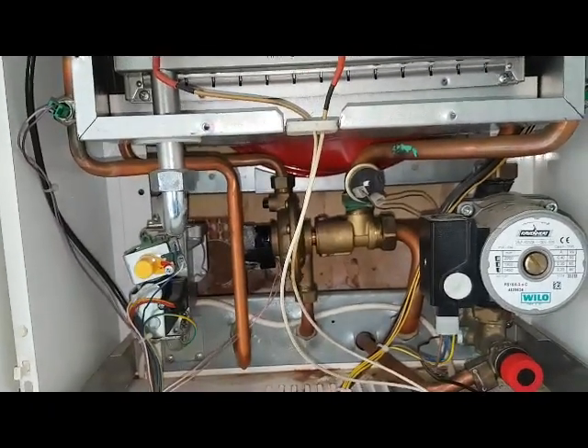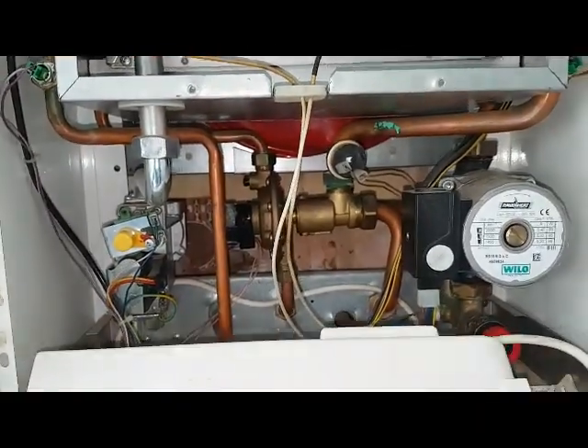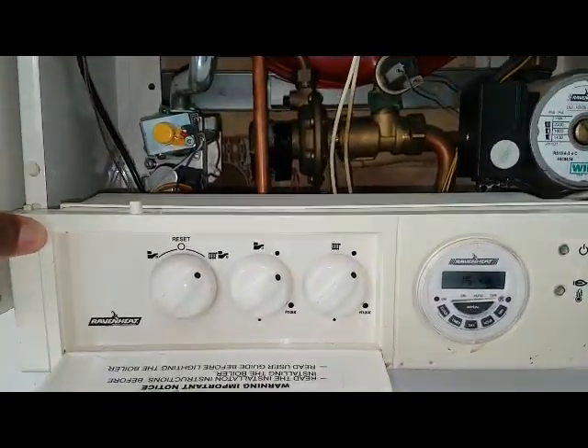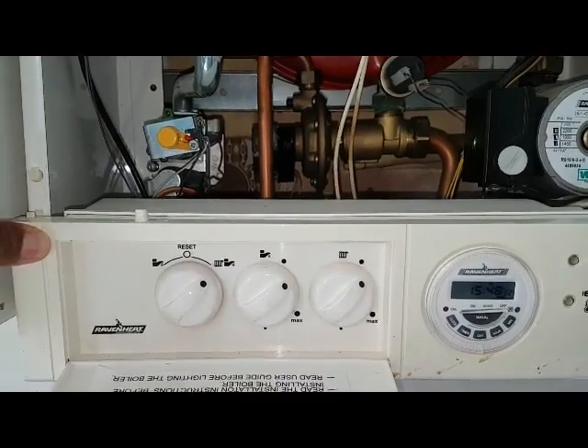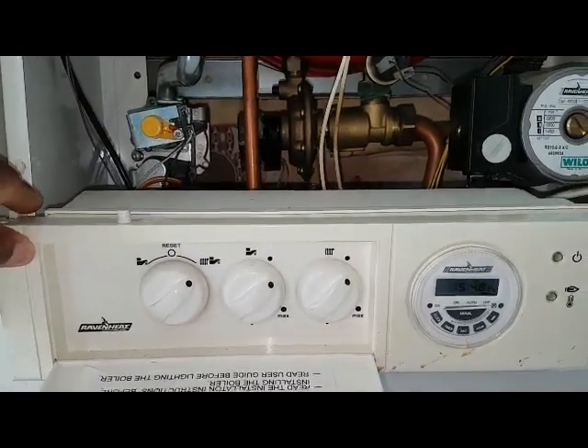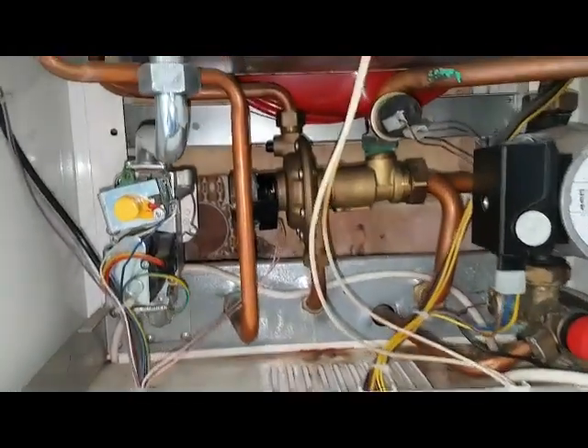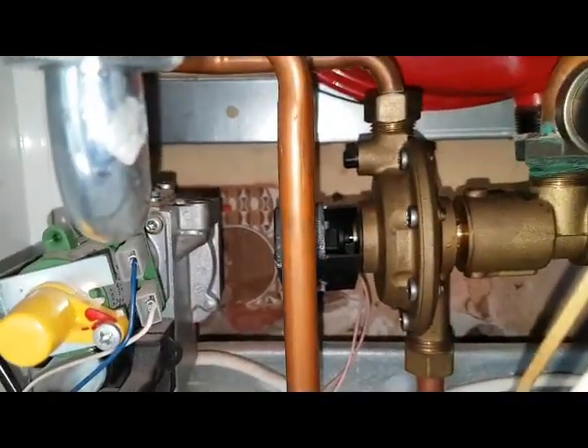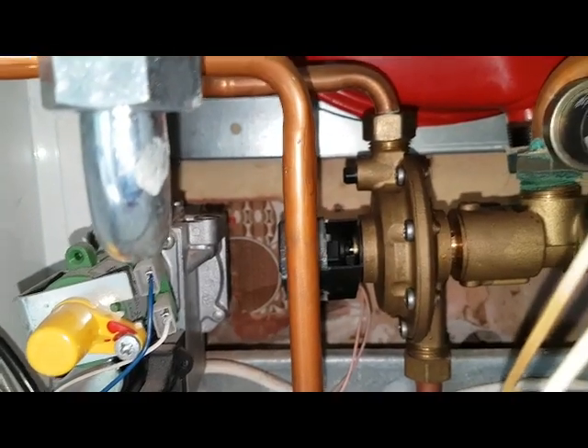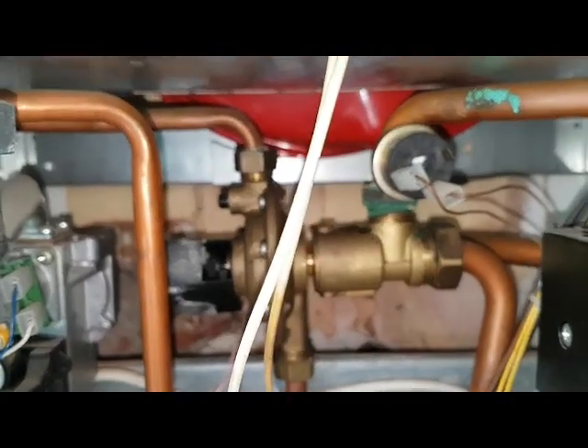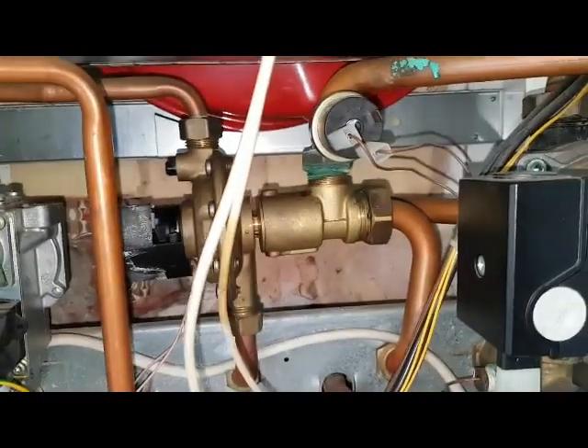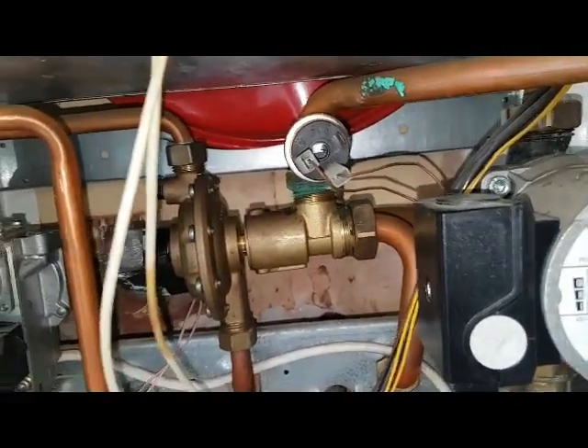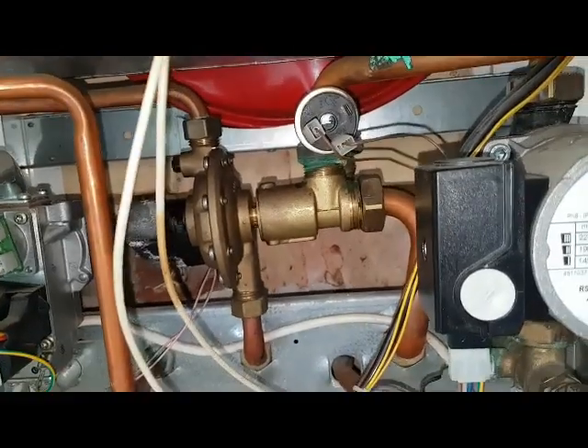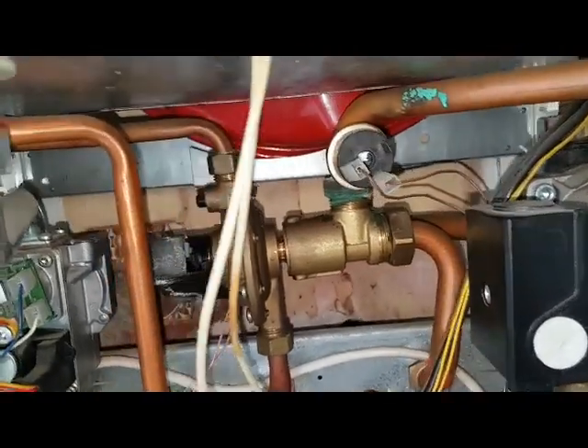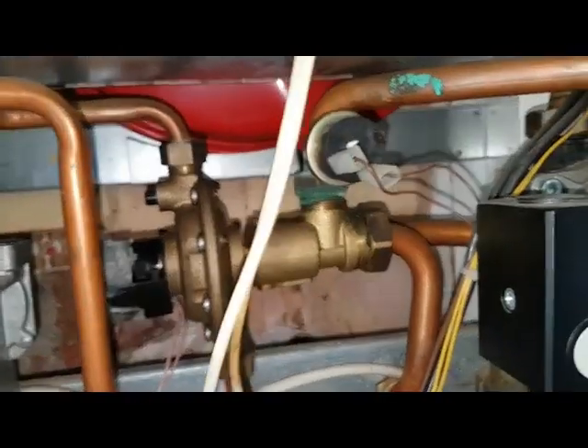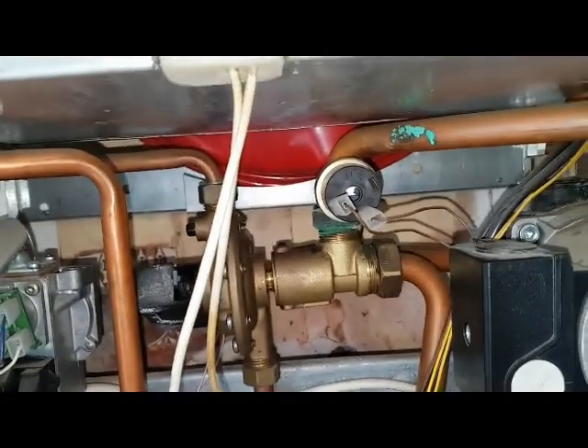So for the hot water function, on the front of the boiler you've got the hot water thermostat, that's going to be calling, and then the tap's going to open. That plunger will push out, make the micro switch. The diverter valve will then move internally. Anything else will work the same, the fan, air pressure switch, as I said before, but the difference is the diverter valve function and the flow of the primary water around the boiler.